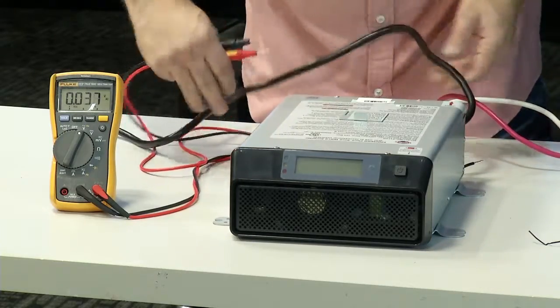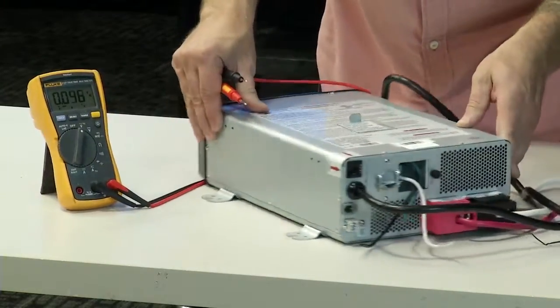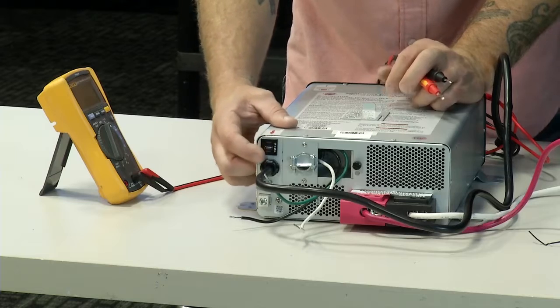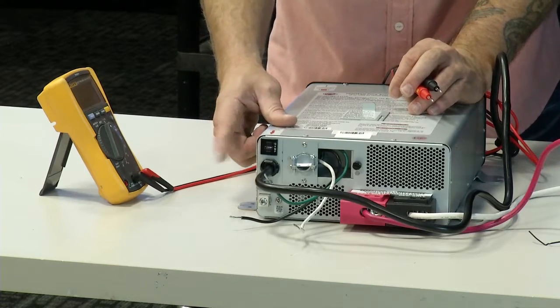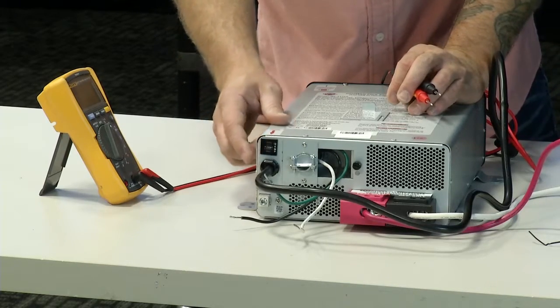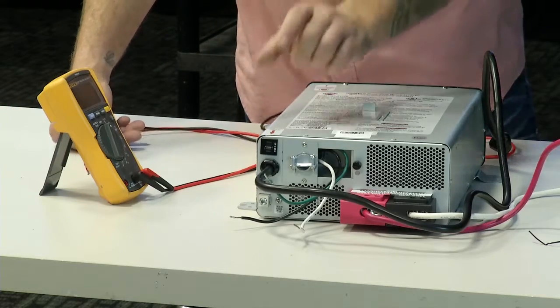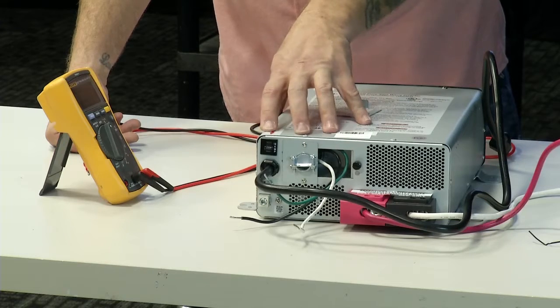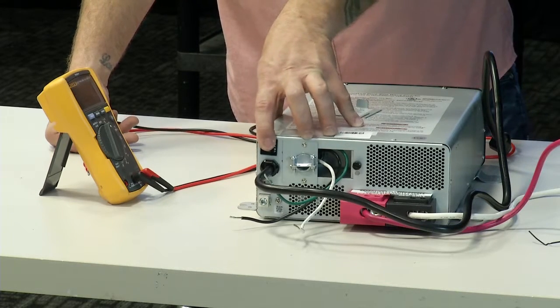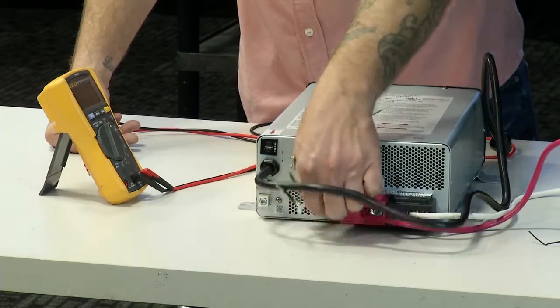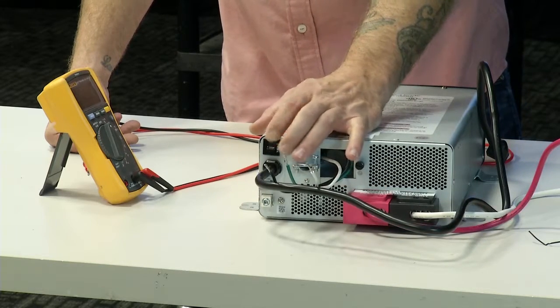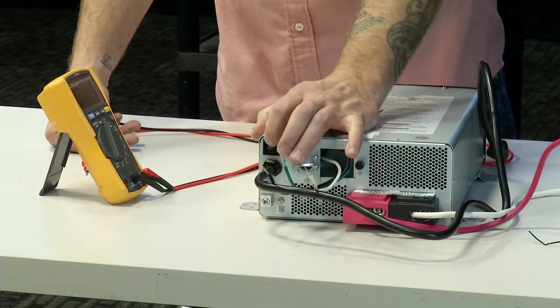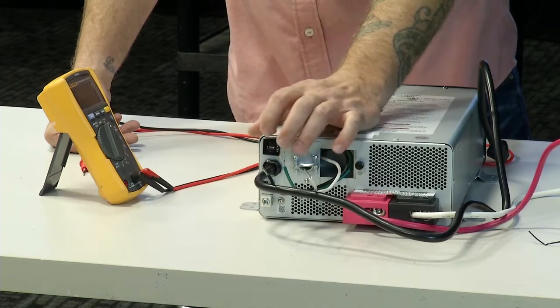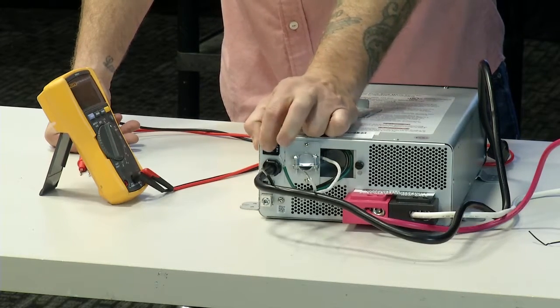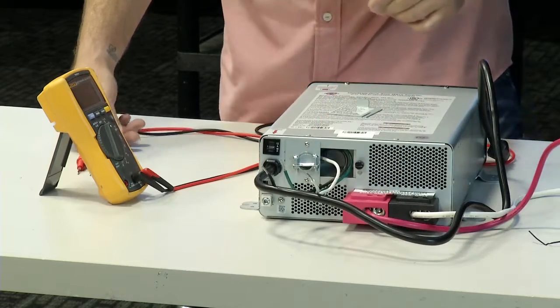And if we spin this inverter around, you'll notice right here there is a little rocker resettable AC circuit breaker, or AC breaker, excuse my language. It is resettable, it's not an auto reset, so this is going to trip if you exceed the amperage of the inverter, or if the inverter is miswired. So if you are not getting output at these wires coming out the back of the inverter right here, always check this breaker. You cannot manually trip this breaker, so I could sit here and push on it. It won't trip the breaker, so you can't test the breaker. But you'll notice when this breaker trips, you'll see a little white edge to it. And as long as you reset it, you'll get your output back at the wires themselves. And that's all we got for an inverter.